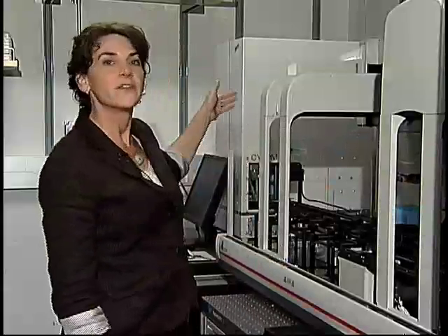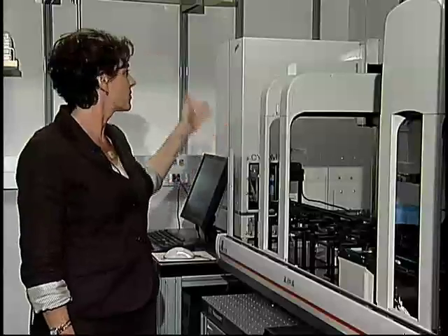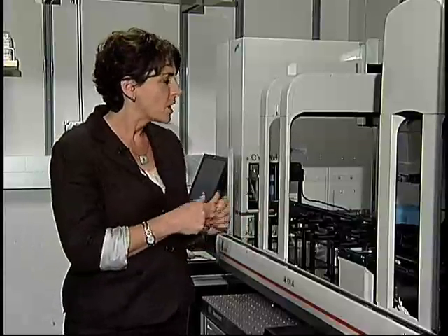Here we have the liquid handler. So these liquid handlers are set up to do automatic pipetting when you have a lot of plates to work with. We have an incubated plate hotel, so your cells can stay warm and cozy in their plates while they're waiting to be processed. And then over in the back, you probably can't see it here, but in the back we have a large plate hotel that holds tip boxes of pipette tips and also plates for processing. So now we're going to go through one of these routines so you can see how the pipetter works.